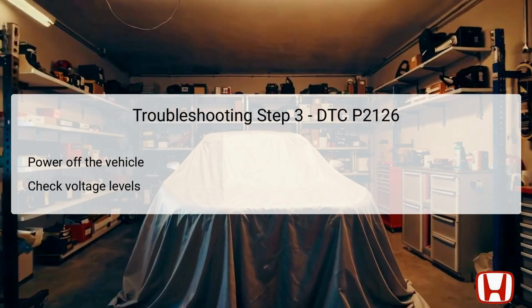You are looking for a voltage measurement of approximately 5.0 volts. If you obtain this voltage reading, it confirms that the power supply is intact to the sensor, prompting you to move to step 4. Conversely, if the voltage does not register as expected, this suggests potential wiring issues that will require further attention.